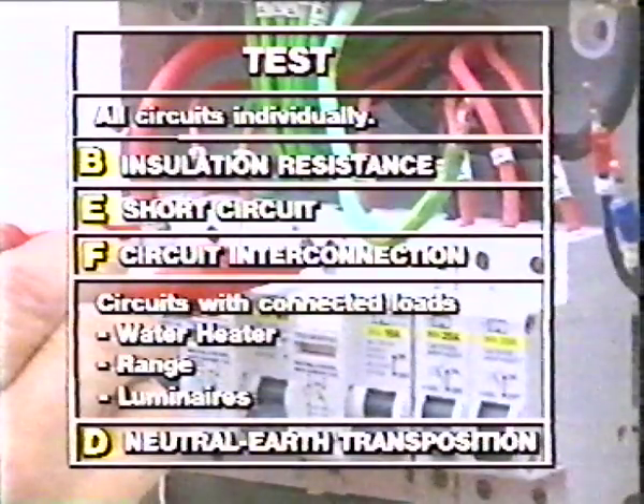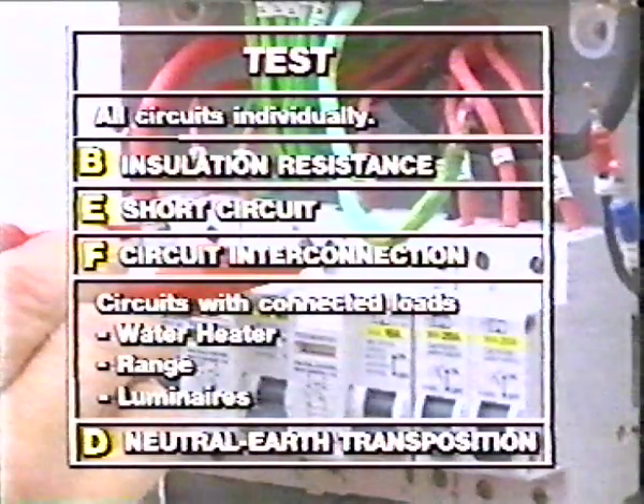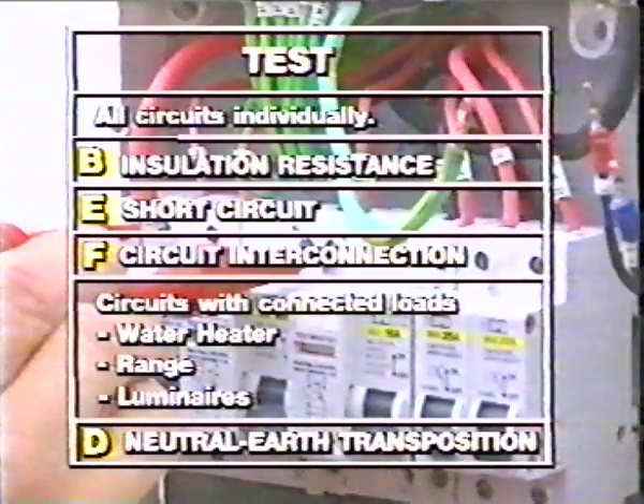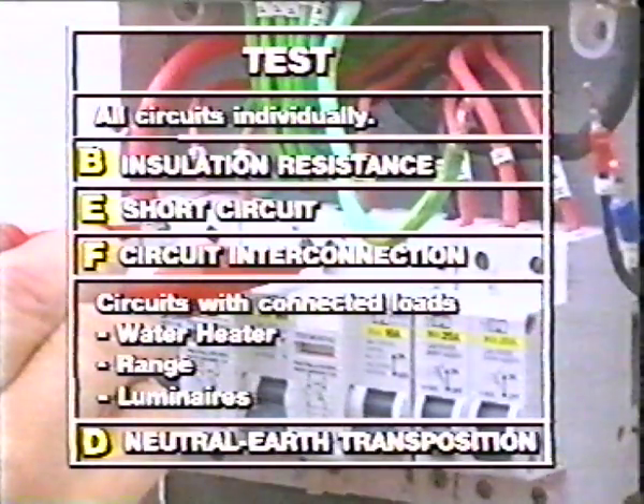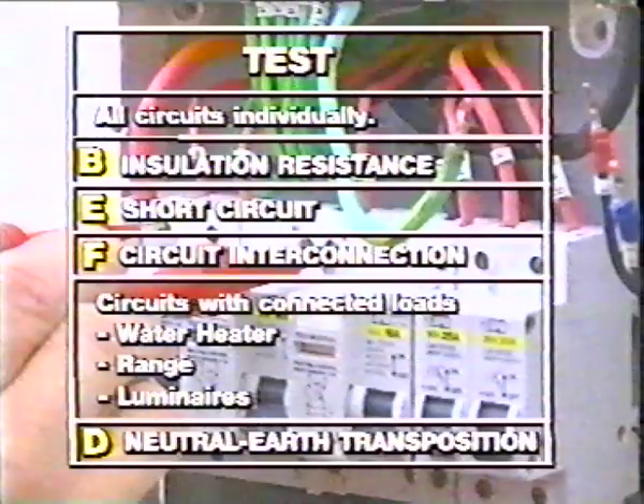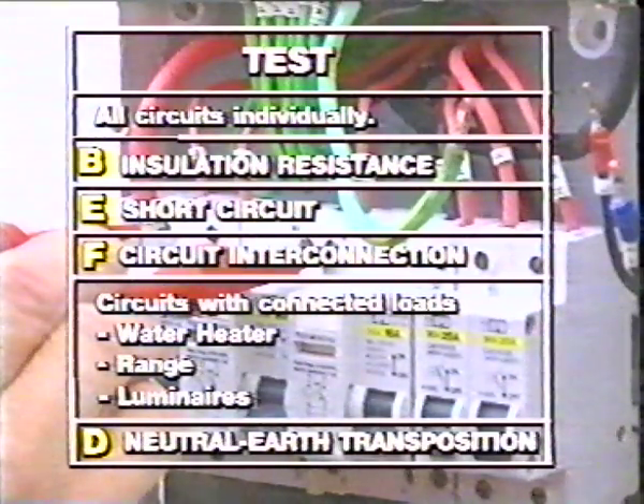Test now for short circuit between conductors as in test E. In this test, an ohm meter should be used rather than an insulation resistance tester, which could cause damage to electronic devices such as lamp dimmers and fan speed controllers.